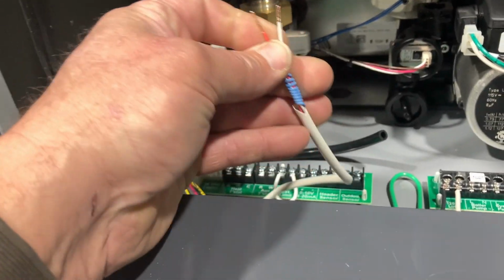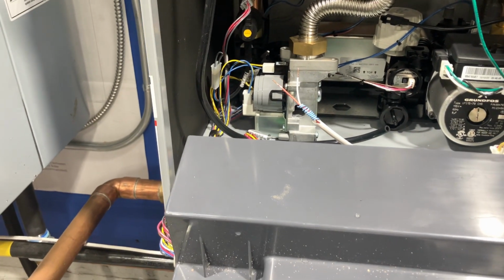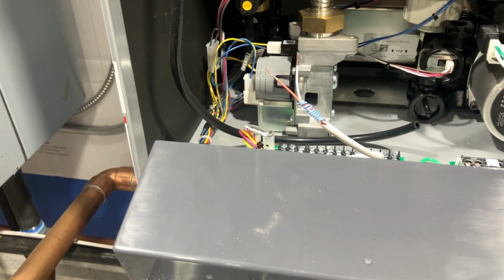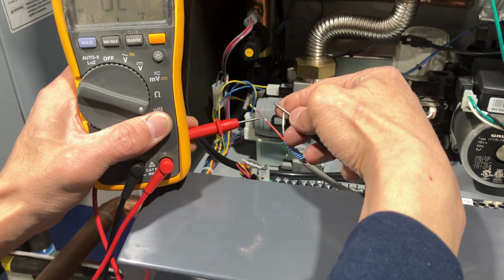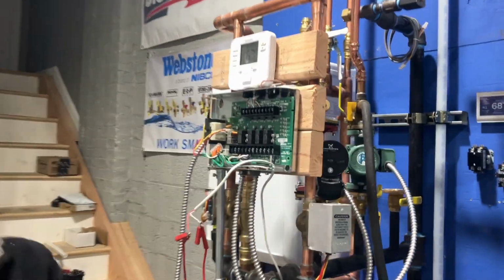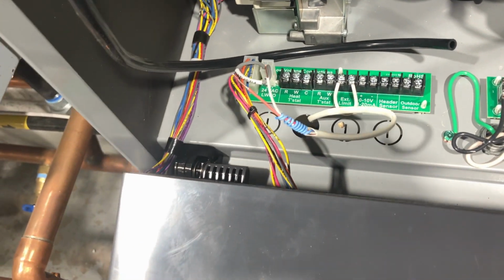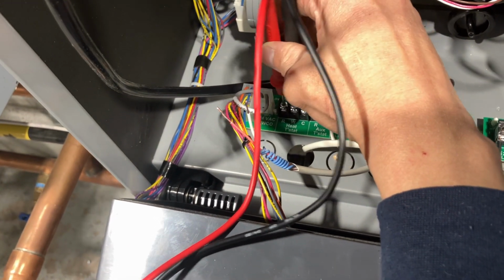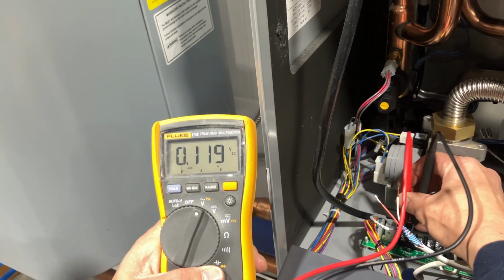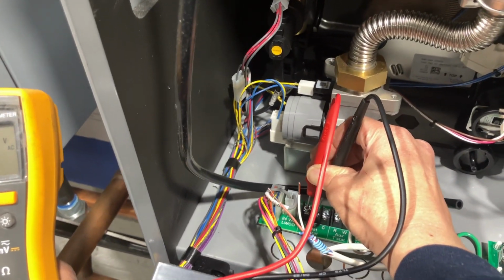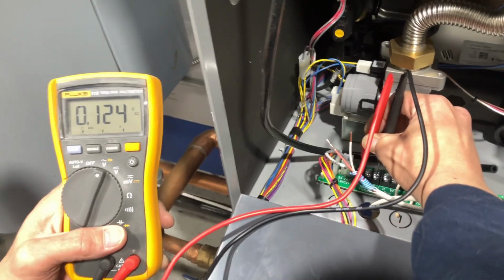Remove the two wires now. Let's test for continuity on these two wires. Ooh. Transformer just popped. Okay, and now check for 24 volts on R and W. No, we don't have 24 volts on R and W. Now go to R and C. R and C. No voltage there. So we got a problem with the boiler as well. So now, we just compounded the problem even more: we have a dead switching relay. We have a dead terminal on our boiler, and it's a brand new install.